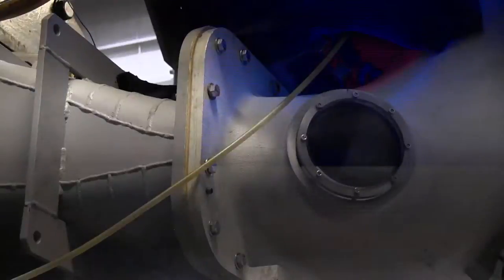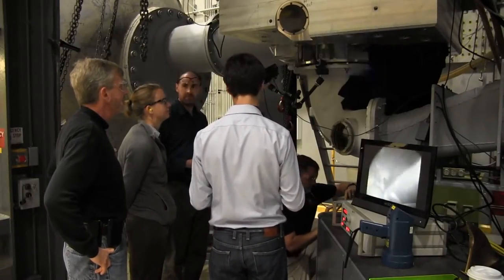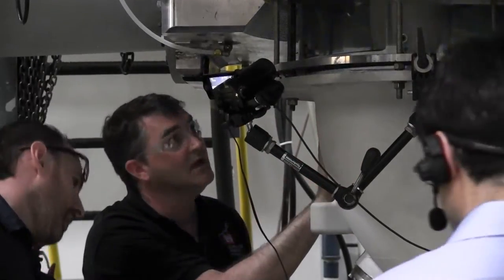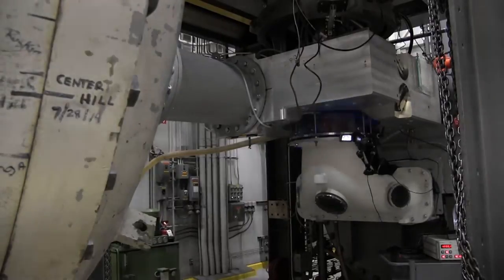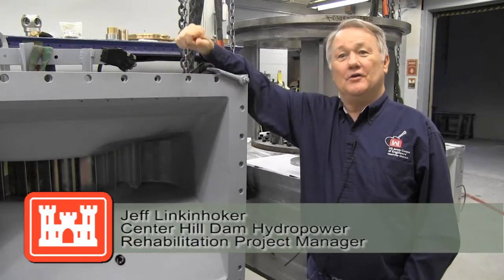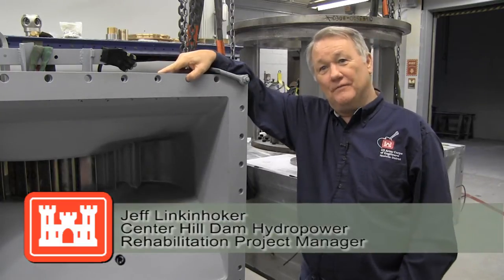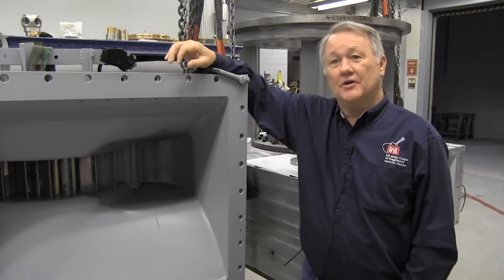Corps of Engineers officials witnessed model turbine tests this week conducted by Voith Hydro. The tests were completely successful, which means the manufacturing process and work to modernize the powerhouse at Center Hill Dam remains on track. They were running it at 224 feet head — we'd have to add another 20-30 feet of height to the dam to even do that. But that's how good their model is.